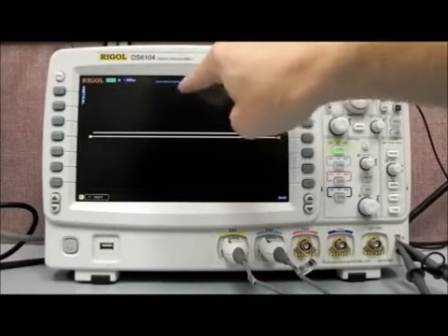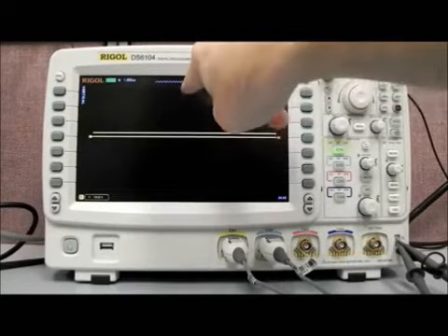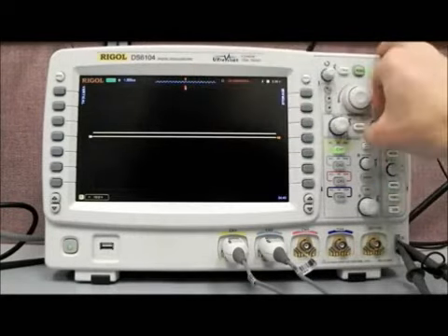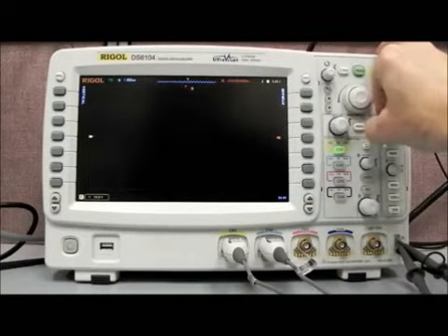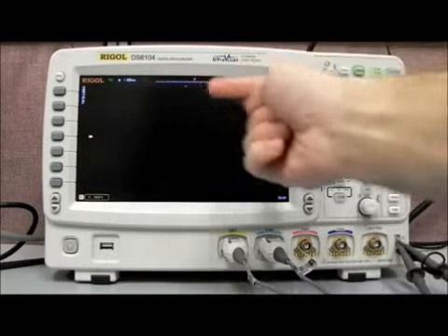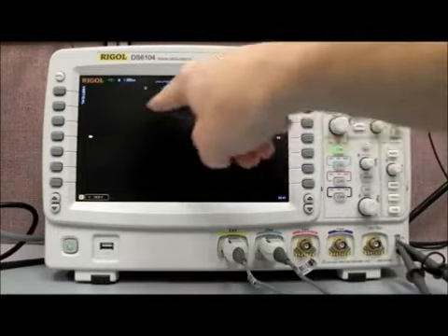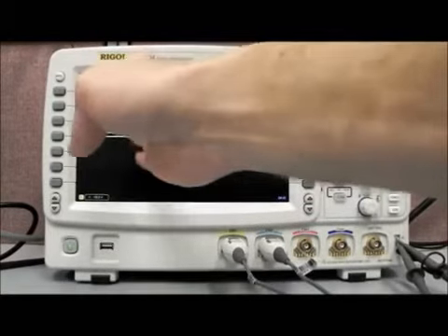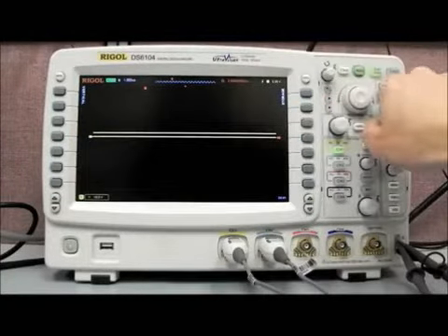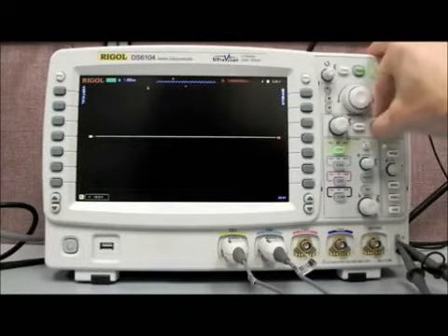The D denotes the distance in time from the trigger point to the actual center point of the display. So you can see as we go counterclockwise, we're actually going in negative time, what's called the pre-trigger area. And if we go the other way, we're going to post-trigger time. Again, this is the trigger, so these are events that have happened after the trigger. And so we'll see we have a positive time-based offset.